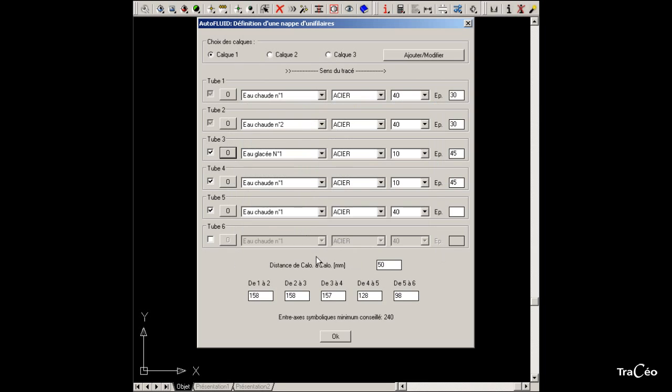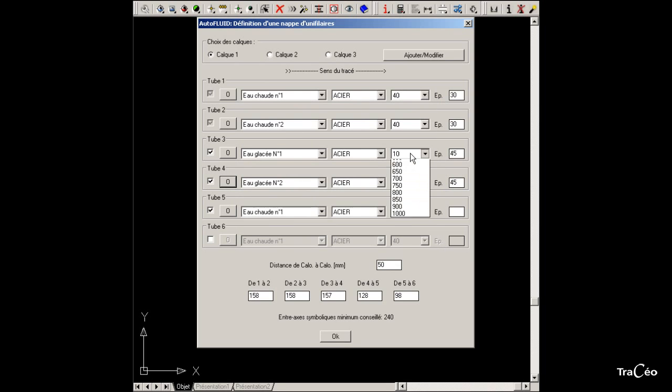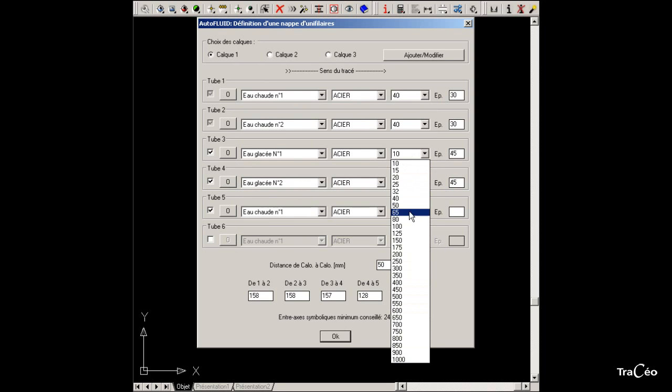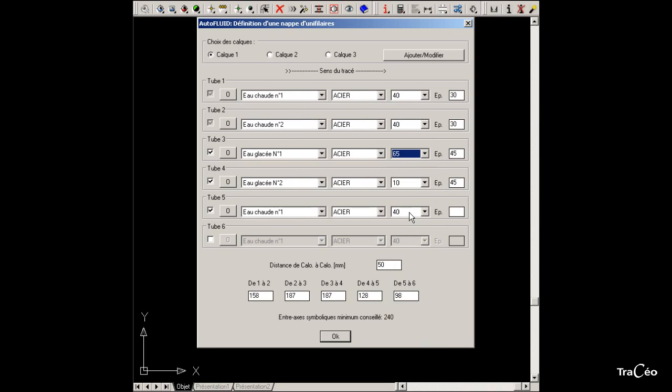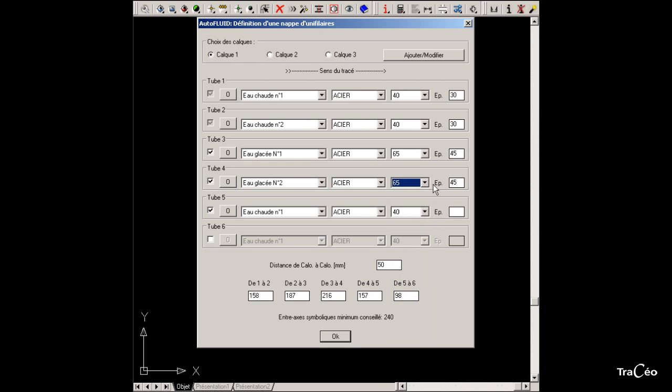The fourth tube is also chilled water so we should assign the layer chilled water number 2. The pipe sizes for chilled water are both 65 and the insulation is 45. Then specify a last tube for condensates.